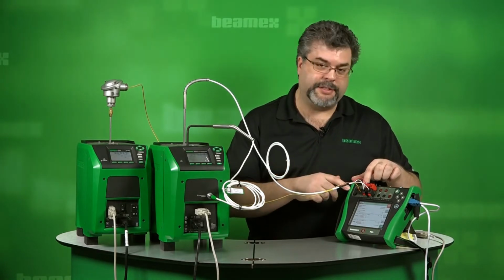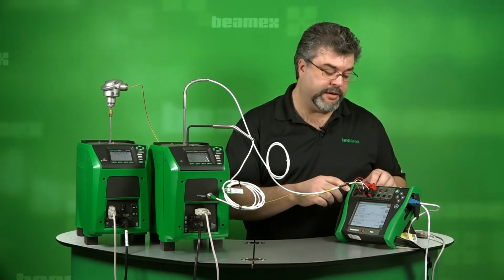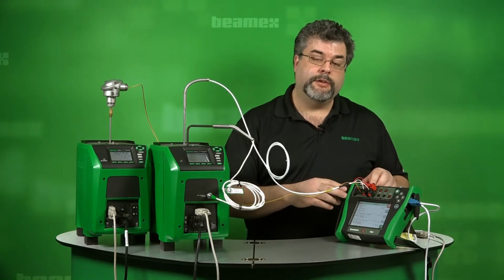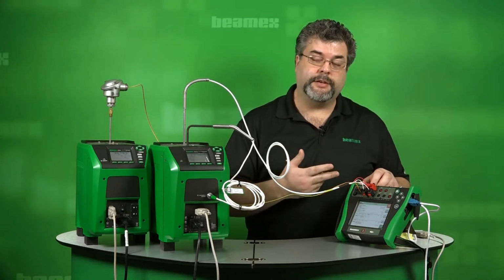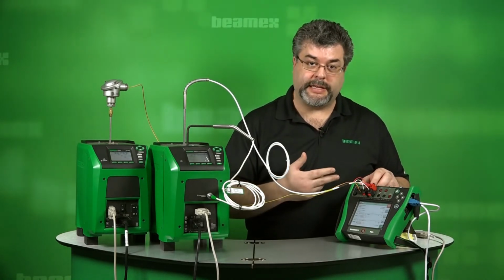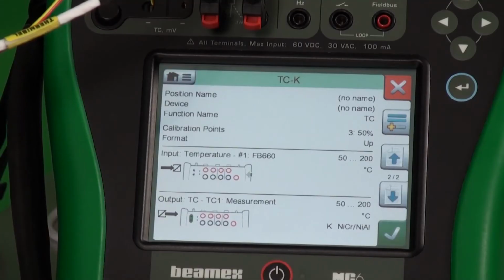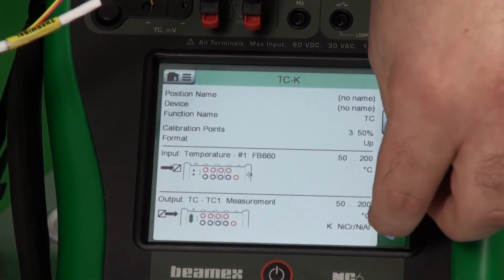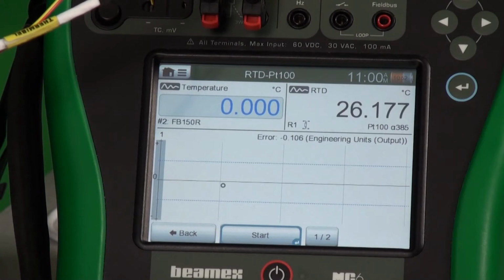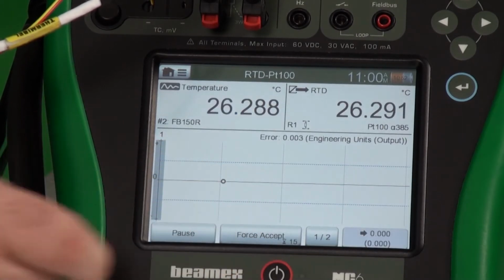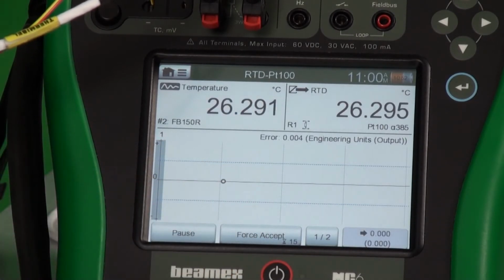Now note, I have a second thermocouple set and a second RTD set that I could use. You could measure 2 thermocouples and 2 different RTDs at the same time. The next step is to hit the check mark. Now once we do this, I've got it set for automatic mode, so I just hit start and wait. It'll do all the work, accept all the points, gather all the data that's necessary.